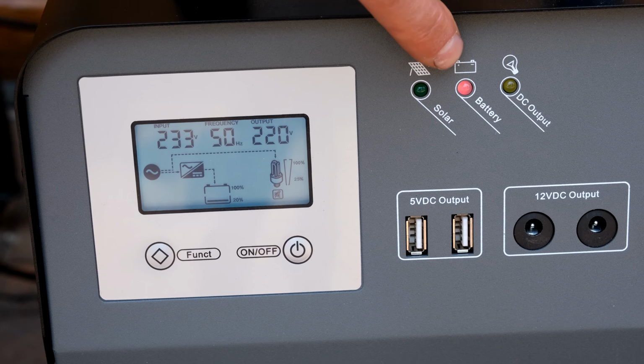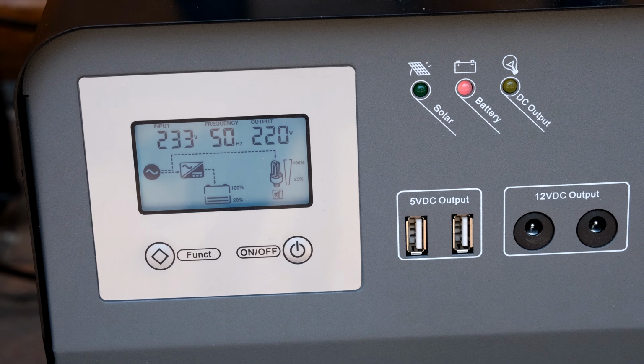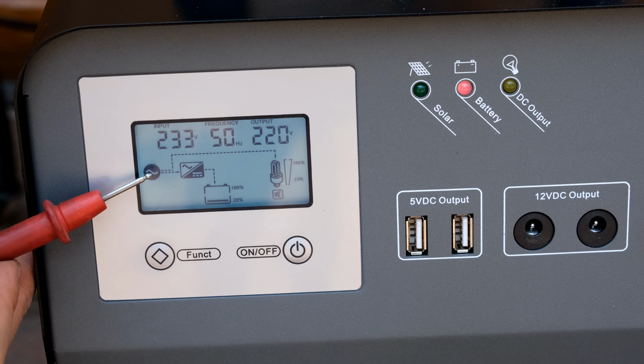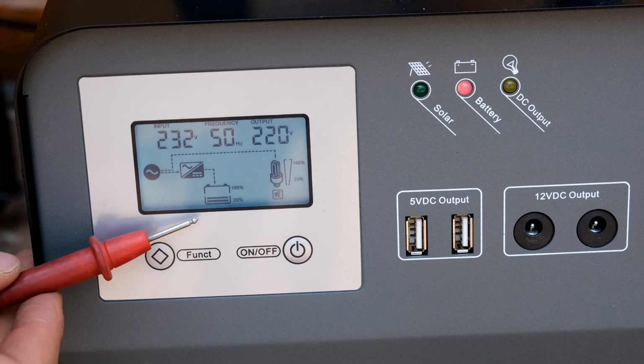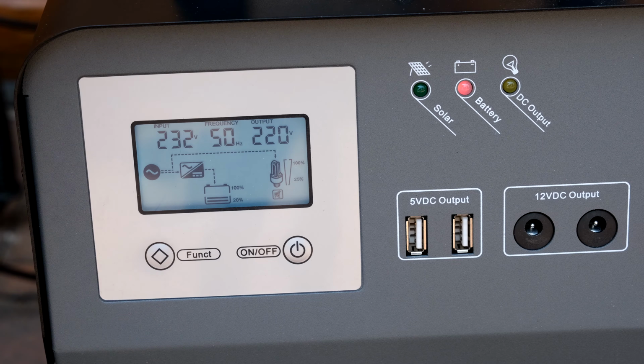It tells me there's something wrong with the battery. The light is on, it's red. A red light means that the voltage at the battery is less than 11.1 volts. In this case, it's 0 because I've disconnected the battery, so that is correct. But surprisingly, the display is still saying it's charging the battery. So I'm going to measure the voltage at the battery.